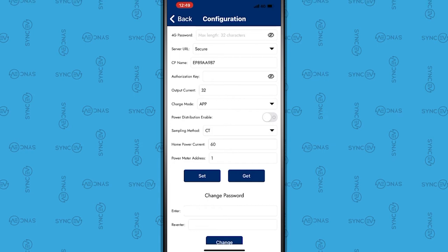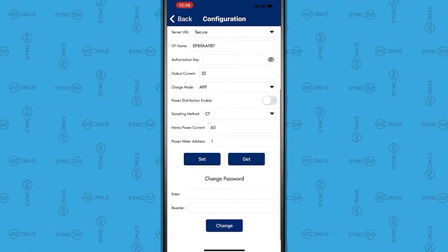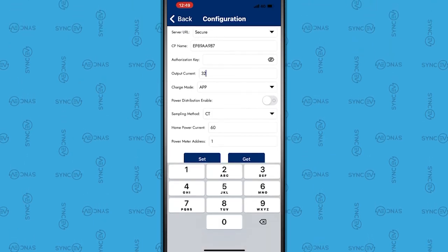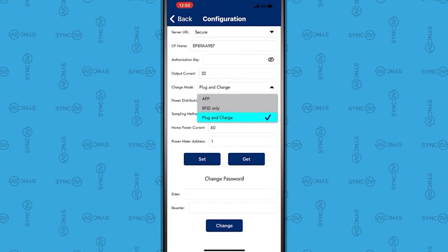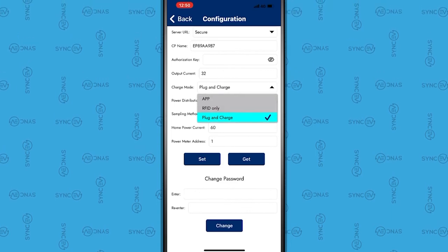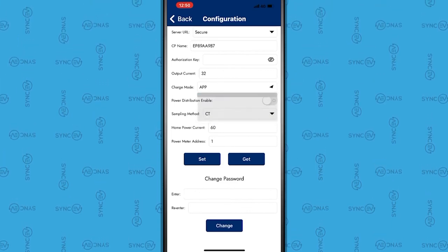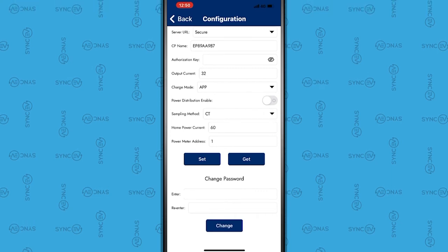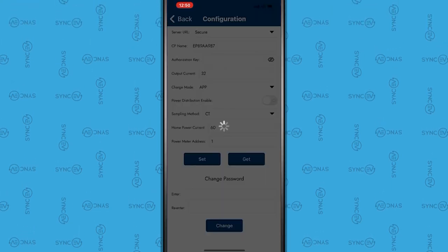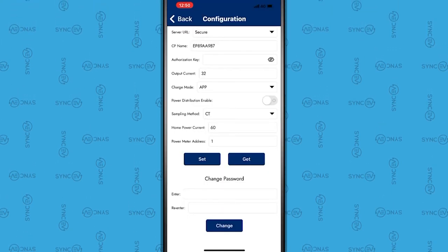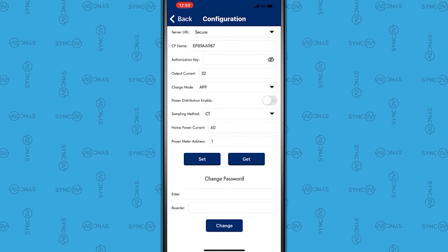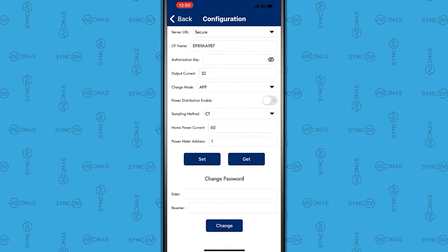The charger's output can be set in the Output Current box. In the Home Power Current box, please input the rating of the property's main supply fuse.